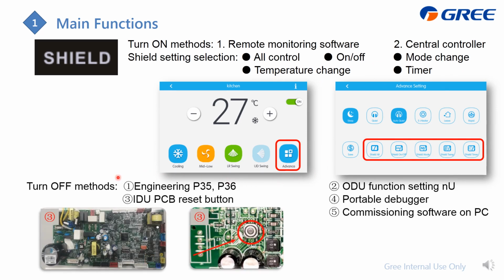And if you would like to turn off this setting, here is how to do it. You can set it from the engineering setting P35 and P36 to reset it, or you can use the outdoor unit function setting to achieve it. Also, on the indoor unit PCB, which is located here, there is a button. Press this button until you hear the beep, which means the reset. You can also set it from the portable debugger or the commissioning software on the PC. It is available to turn off this shield function.